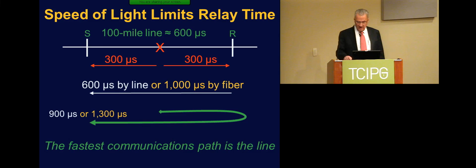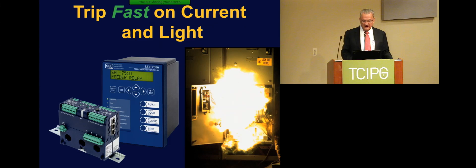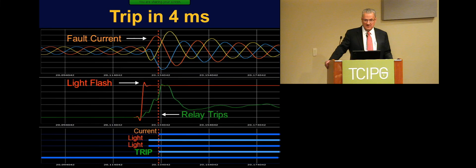Here's another point that we've had great success. Arc flash, unfortunately, kills somebody every day in this country. So you've probably heard about arc flash hazards. So here's a protective relay, 2 of them actually, that operate on current and light. In this oscillogram, you can see the fault current appearing in all 3 phases. And the middle trace there shows you the light flash intensity as a red trace that jumps up there in a hurry. So we use a combination of light and current, so we don't have to wait for any fuse to blow or any time coordination whatsoever, and this technology saves lives.